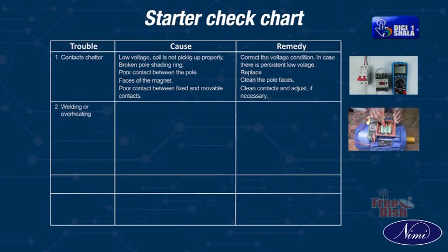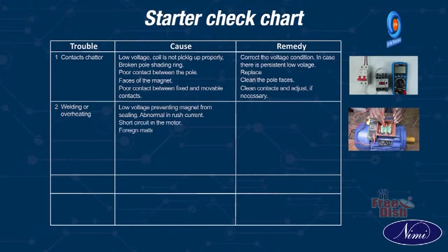Trouble. Number 2. Welding or overheating. Cause. Low voltage preventing magnet from sealing, abnormal inrush current, short circuit in the motor, foreign matter preventing contacts from closing, rapid inching. Remedy.